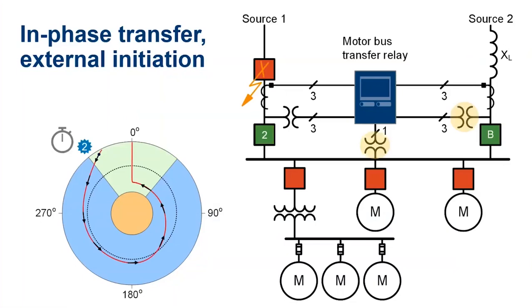There is a time delay there, and that will cause the phase to fall outside of the initial window. So by the time we can start doing the in-phase transfer, the phase difference is too big. And so we need to wait for the phase to realign with the other system. So we coast with both breakers open for a while until we determine, by measuring the phase, the frequency, and the rate of change in frequency, that it's an appropriate time to send the close command to the other breaker.